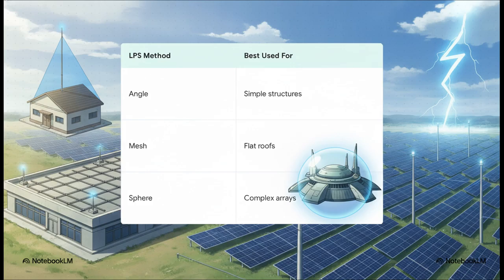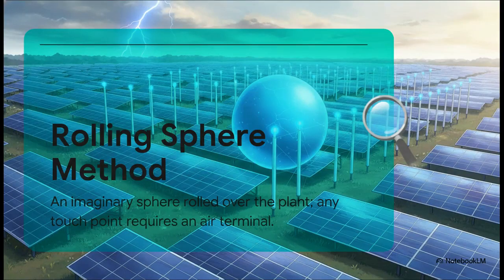But when we're talking about a massive utility-scale solar plant, one of these methods absolutely reigns supreme as the industry best practice. And that is the rolling sphere method. Imagine this for a second. The standard dictates that for a basic Class 4 lightning protection level, we mathematically take an imaginary sphere with a 60-meter radius and basically roll it entirely over your solar array. Any point on your plant where that imaginary sphere actually touches is a point that's vulnerable to a direct lightning strike, and that means it requires an air terminal, a mast, to be placed right there. In a typical 60-megawatt plant example, this geometry might tell you to place a grid of, say, exactly 169 masts, each 12 meters high, perfectly spaced so that sphere never touches the solar panels themselves. It's like a giant invisible force field you're designing.